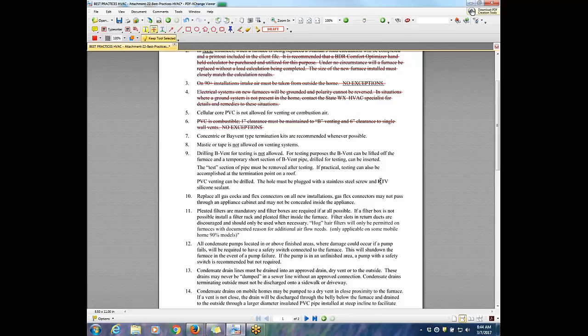All right, so number 8, no one has a problem with that. Let's see. Number 9, this is the big one here. This has come up a couple of times lately. So, drilling Bvent for testing is not allowed. I disagree with that 100%, and I still stand behind that comment. I don't have a problem with you guys drilling Bvent. If you understand how a Bvent system works, you realize that drilling a hole in it doesn't hurt it. Case in point, a water heater has a big giant hole in the venting system. It's called a draft hood.